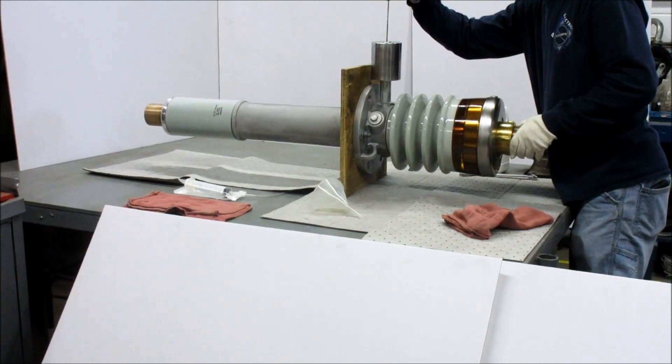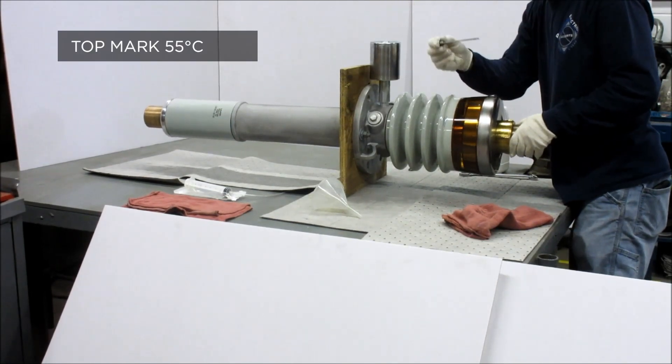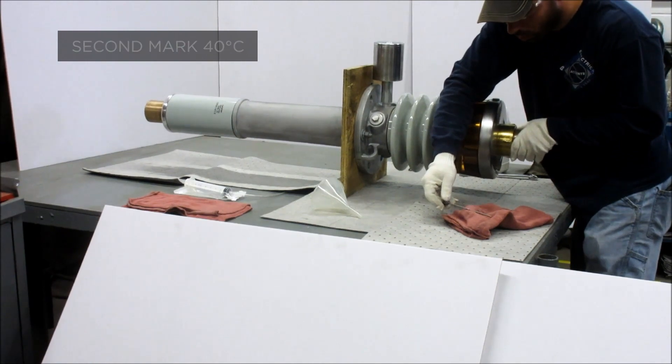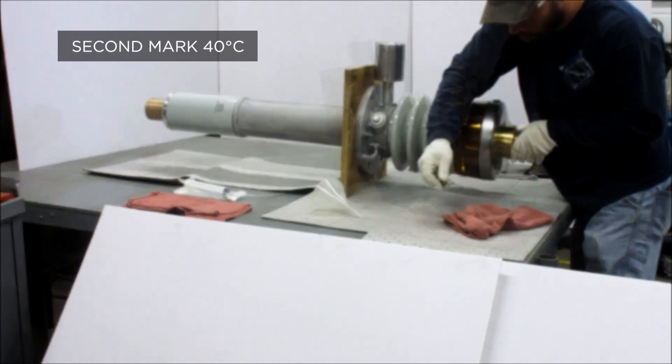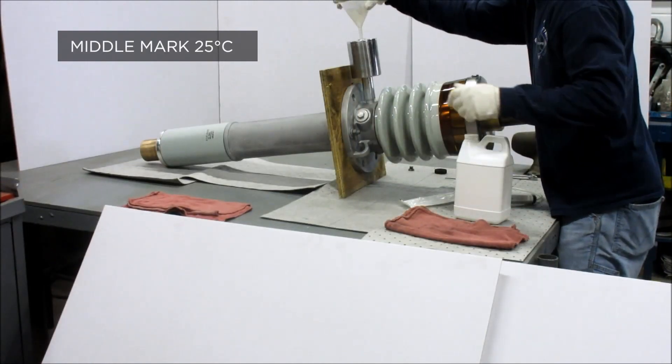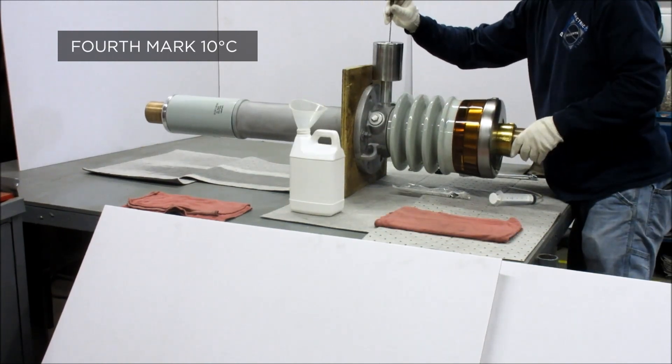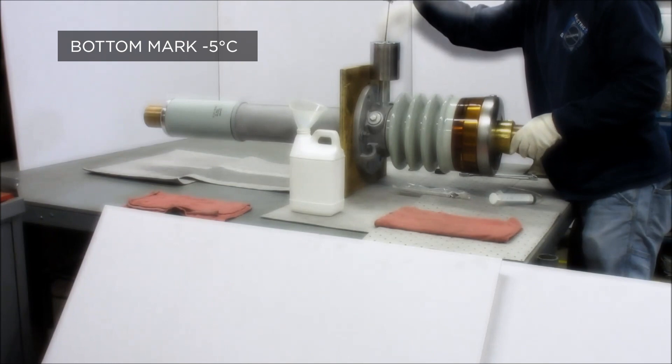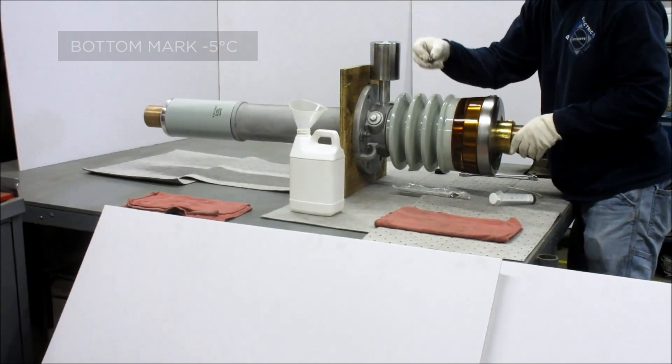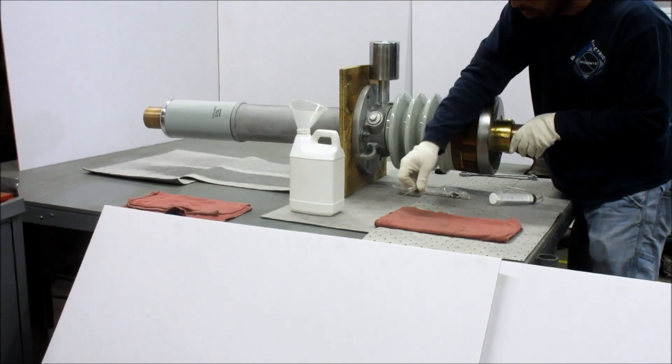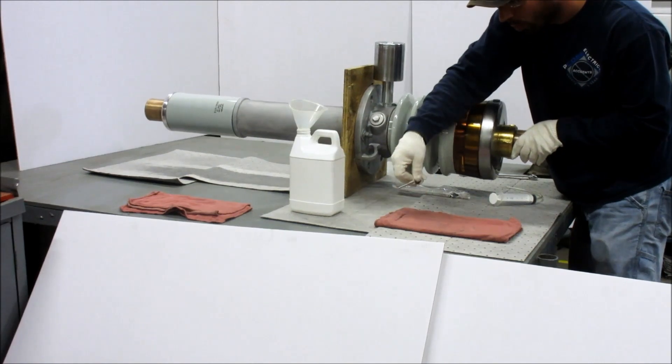Use the dipstick to measure the oil level. The top mark is for 55 degrees Celsius, the second for 40 degrees Celsius, the middle for 25 degrees Celsius, the fourth for 10 degrees Celsius, and the bottom for negative 5 degrees Celsius oil temperature. Interpolation between marks is not critical. If in doubt, use slightly less oil.